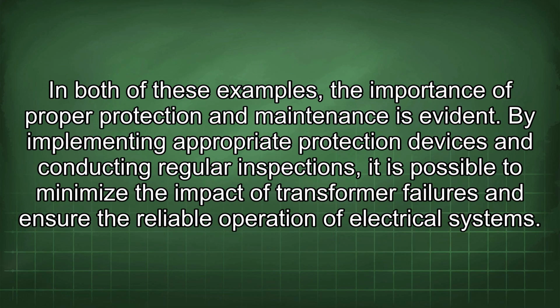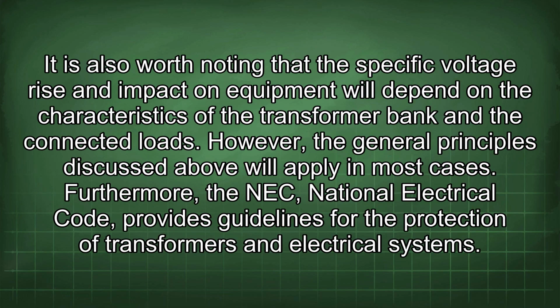In both of these examples, the importance of proper protection and maintenance is evident. By implementing appropriate protection devices and conducting regular inspections, it is possible to minimize the impact of transformer failures and ensure the reliable operation of electrical systems. It is also worth noting that the specific voltage rise and impact on equipment will depend on the characteristics of the transformer bank and the connected loads. However, the general principles discussed above will apply in most cases.